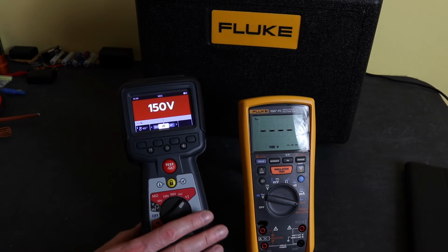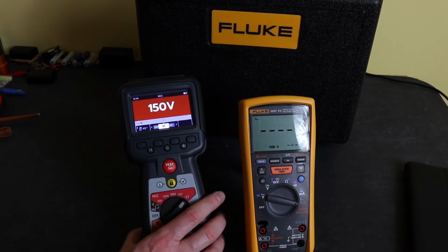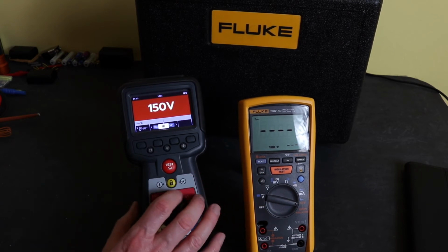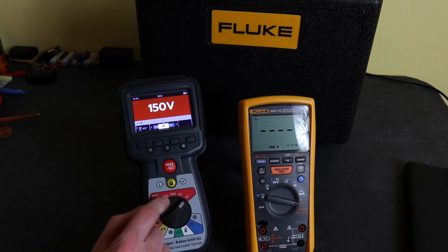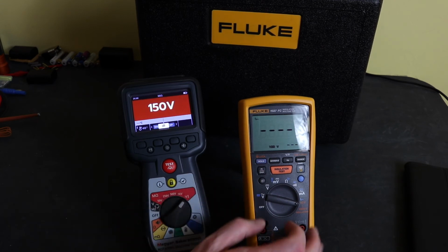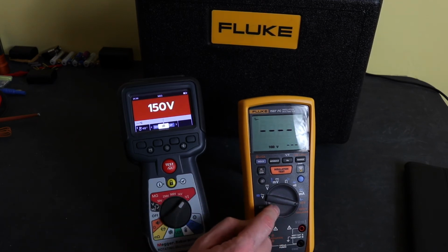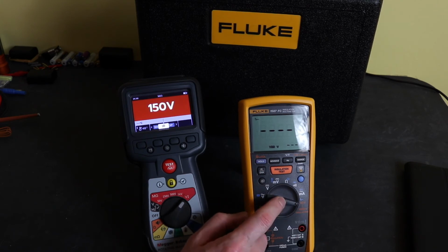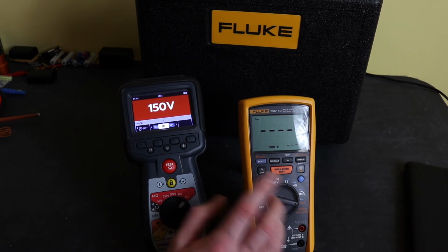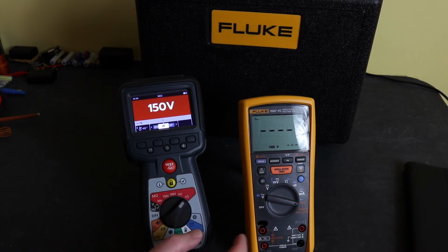In terms of accuracy on the insulation testing, this instrument has a much wider range, up to 200 gig ohms at 1kV, 100 gig ohms on the 500 volts. And this 1587 only goes up to 2 giga ohms at 1000 volts. It's down to 550 mega ohms at the 500 volt range and continues to go down to below that for the lower voltage ranges.